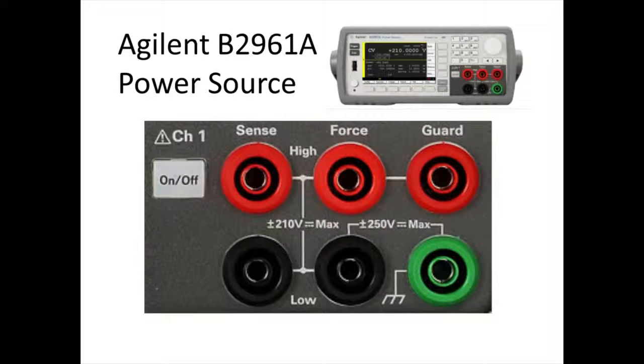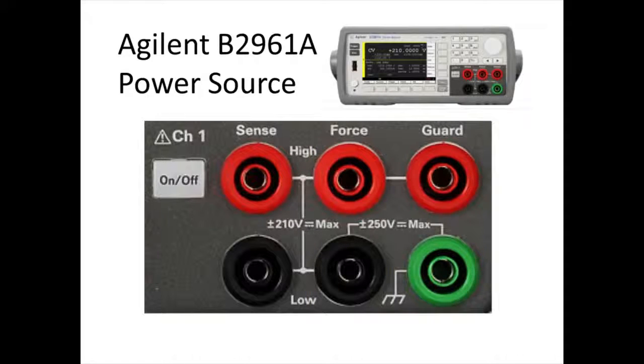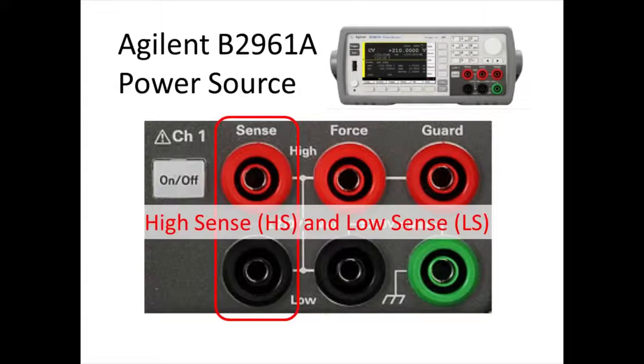This is an enlarged view of an output terminal panel. There are six output terminals on this panel. The force terminals are used for applying current and voltage to a DUT. Voltage and current are applied between high force and low force. When you use remote sensing, you need to use the sense terminals. Then you can eliminate the voltage drop across lead resistance and apply the voltage as expected.